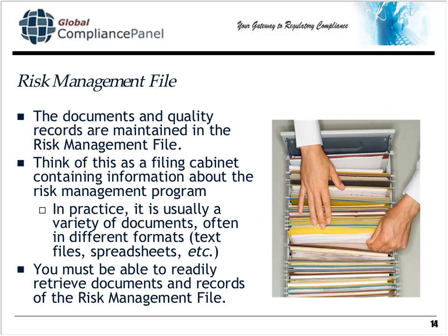Today, it's more likely going to be electronic documents that are usually going to be in different formats, text files, spreadsheets, whatever. What's really important is that you know where they are and you can readily retrieve them when necessary. And one of the places it's going to be necessary is if you have an FDA inspection or a notified body audit, they are going to ask you for all of this documentation in your risk management file.